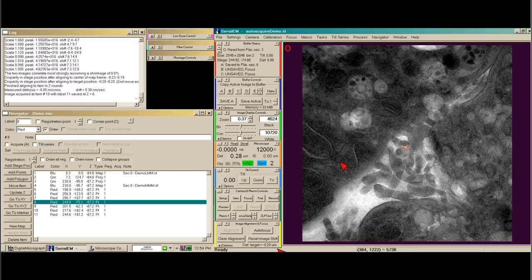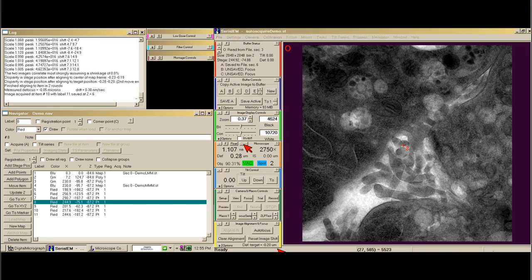Now I have to do something extremely important before I take my tilt series: I need to bake out the sample and cook it so that it shrinks laterally in X and Y and also goes through the small amount of thinning in Z that happens during tilt series acquisition. I'm going to lower the mag, spread out my beam, and open up this box called the dose meter. This dose will show how much dose has been added to the sample. We're essentially at 1,500 electrons now, and all I have to do is raise the screen and it stops the count because the beam is blanked.